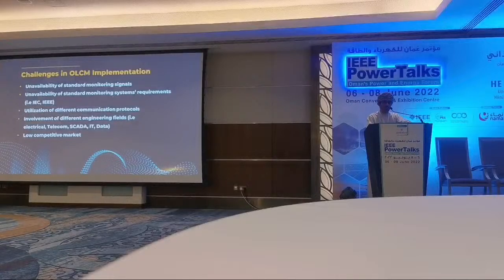This is the main challenge we have faced, because not all manufacturers have standard monitoring signals. Also from our side, there was no standard monitoring signals. So some transformers, if we have two transformers at the same voltage level, they may have different monitoring signals, and integrating different monitoring signals is a challenge during implementation.